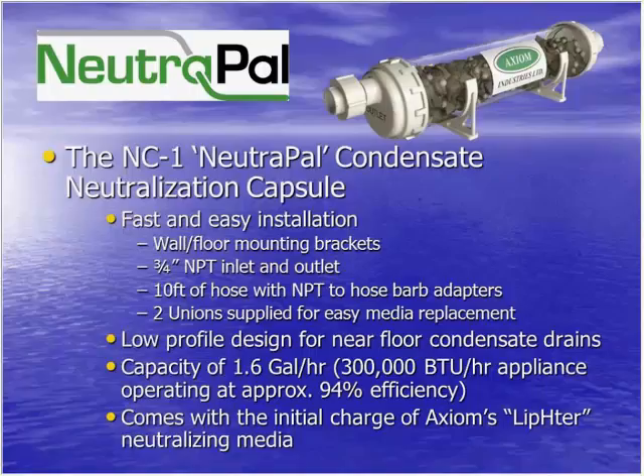And the capacity of this unit is 1.6 gallons per hour. Now that's approximately 300,000 BTU per hour, operating at approximately 94% efficiency. And the rule of thumb in the industry is for every 100,000 BTU per hour, you can potentially get 1 gallon per hour of condensate. Now that's if the heat exchanger is operating at 100% efficiency, if the combustion there is saturated, it's very humid. So in real world conditions, appliances are, if possible, at their AFUE efficiency, typically in the low to mid 90s. So the actual condensate capacity is usually a fair amount less.